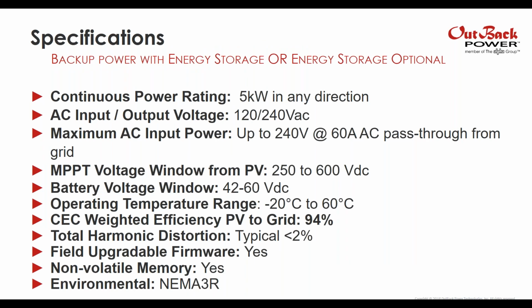So specifications. 5 kW in any direction, 120/240. Maximum AC input power is 60 amp on pass-through. So if you need a high surge load to be supported, it can come from the grid or from generator. MPPT voltage window from PV, 250 volts all the way up to 600 volts. Battery voltage window range, 42 volts up to 60. So it covers all of your traditional lead acid batteries. Very wide operating temperature range, CEC weighted PV efficiency from PV to the grid over the entire PV voltage window range, 94%. Excellent total harmonic distortion, field upgradable firmware.